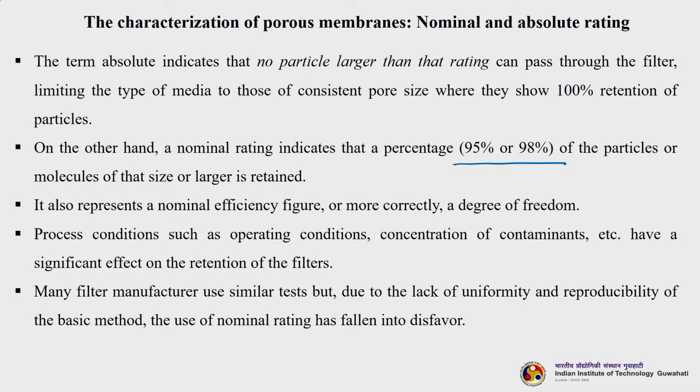It also represents a nominal efficiency figure or, more correctly, a degree of freedom. Process conditions such as your operating conditions and concentration of your solutes have a significant role in the retention of the filters. Many filter manufacturers use similar tests, but due to lack of uniformity and reproducibility, the use of nominal rating has fallen into disfavor. So, mostly whatever ratings we see nowadays are all absolute ratings.